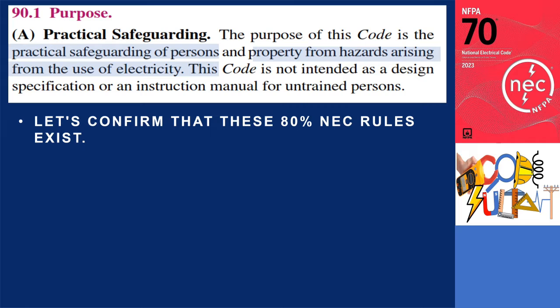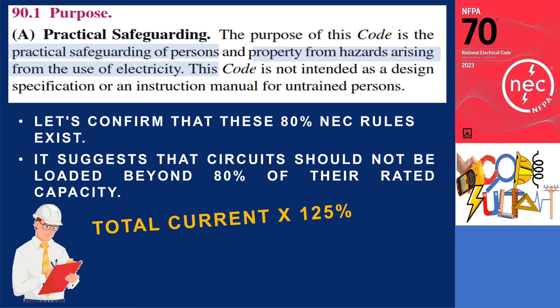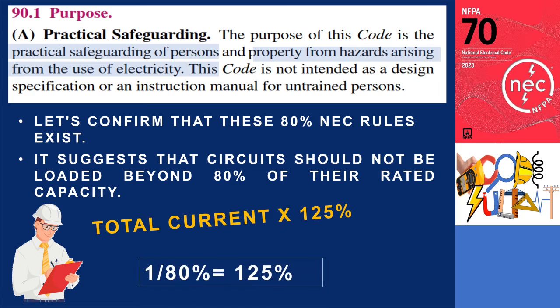The purpose of the NEC is to safeguard lives, protect property, and promote electrical safety through comprehensive and up-to-date guidelines for electrical installations. The 80% rule ensures that circuits operate within a safe range, accounting for the capacities of all components within the circuit. It suggests that circuits should not be loaded beyond 80% of their rated capacity. This is why some practitioners multiply the total current by 125%, which is the inverse of 80%.